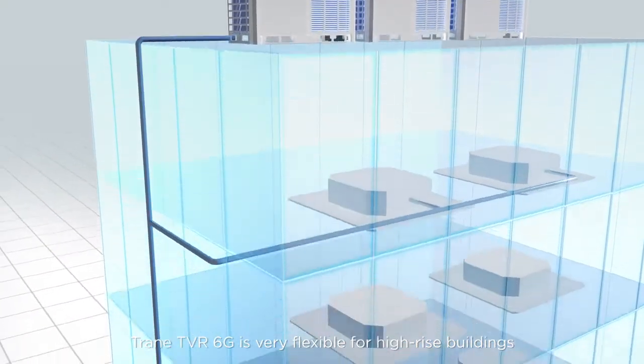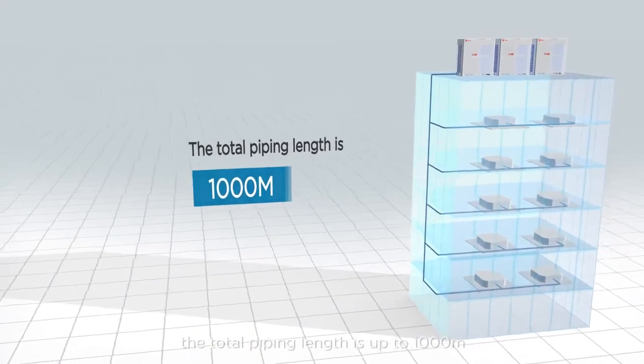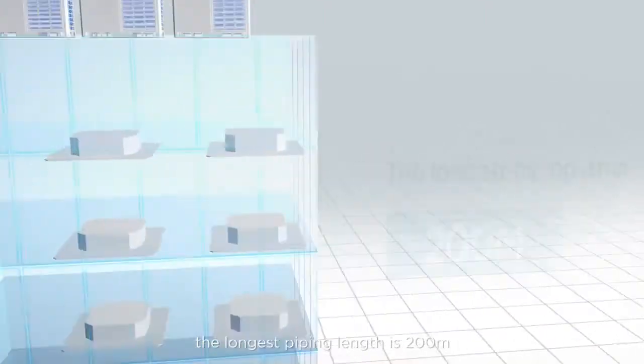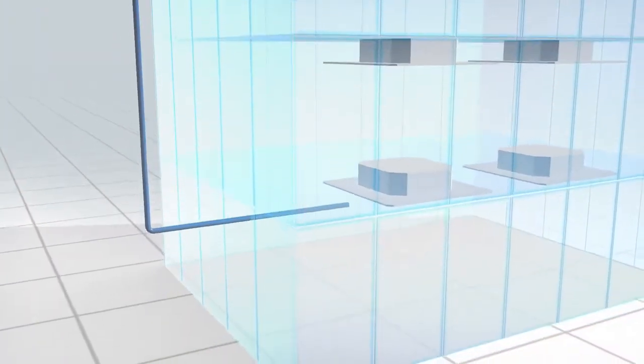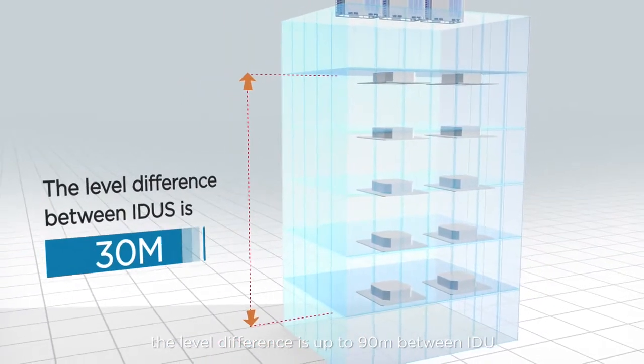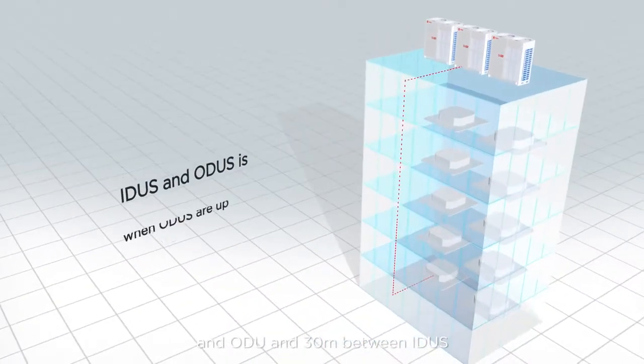Trane TVR 6G is very flexible for high-rise buildings. The total piping length is up to 1,000 meters. The longest piping length is 200 meters. The level difference is up to 90 meters between IDU and ODU and 30 meters between IDUs.